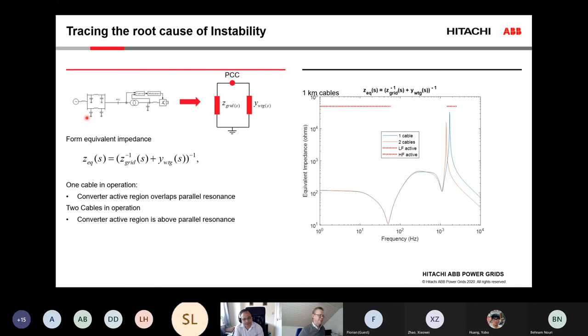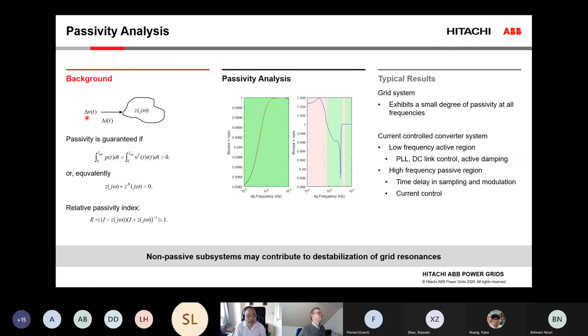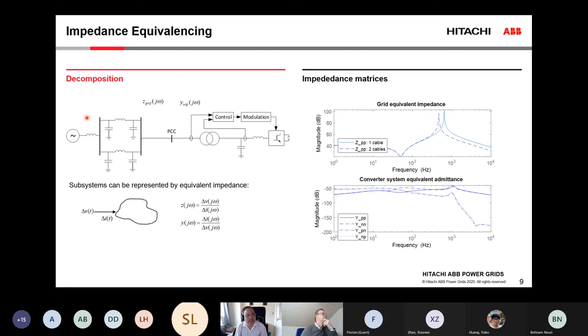So if you go back to that slide 9 again, I also had another point to ask. Yes. So the point of common coupling, you had a slide number 9. This one? Yes. So this is about the impedance estimations. At the point of common coupling, you are giving, at the bottom, delta V by delta I. Now, depending on the relative capacity of the grid on the left and also the capacity of the power converters, whether it is coming from a wind farm or something, getting the impedance estimated would be tricky for two reasons. We experienced this, but I want to share your view on that.